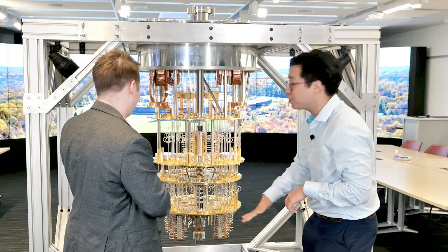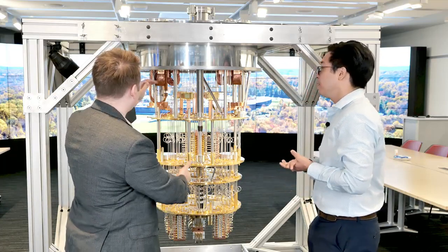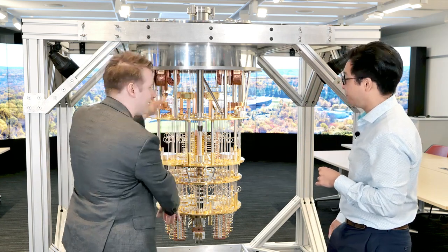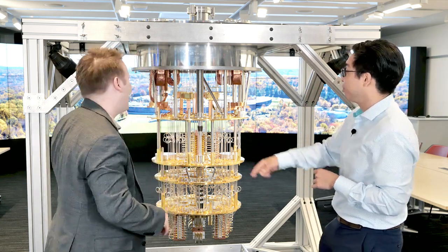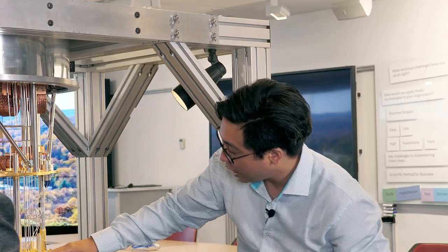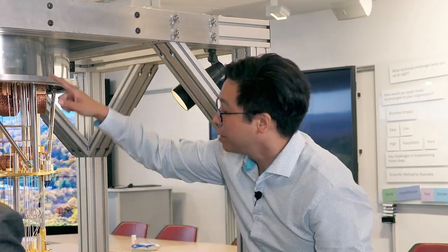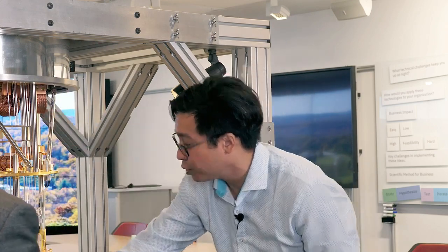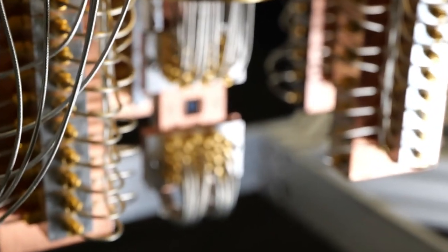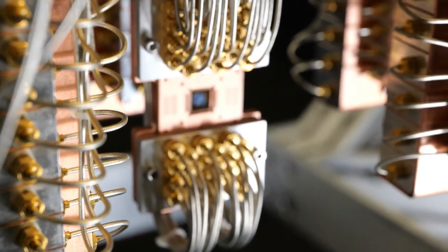Okay. So all these different plates are actually at different temperatures. So you've got determined thermal zones, one here, one here, one here, one here, and you're decreasing as you go down. Exactly. You got it. So room temperature, around 50 to 60 Kelvin, 4 Kelvin, 800 millikelvin, 100 millikelvin, and then 15 millikelvin. The second stage refrigerator is here. It's called the actual dilution refrigerator. And it's what gets us down to that lowest temperature for the quantum chip that sits all the way at the bottom. Oh, wow.